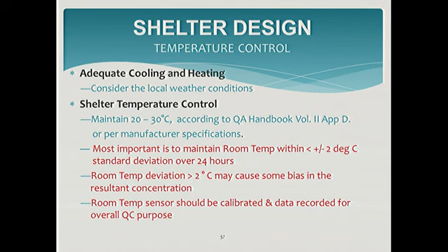This is the Met One chart elaborating on the sampler improvements made to the older BAM samplers, minimizing the effect caused by an 8-degree swing in room temperature. So if your sites have room temperature fluctuations between 20 and 30 degrees, which is kind of normal across the board, the resultant data is still valid, and this is also per the guidance that EPA gives us.